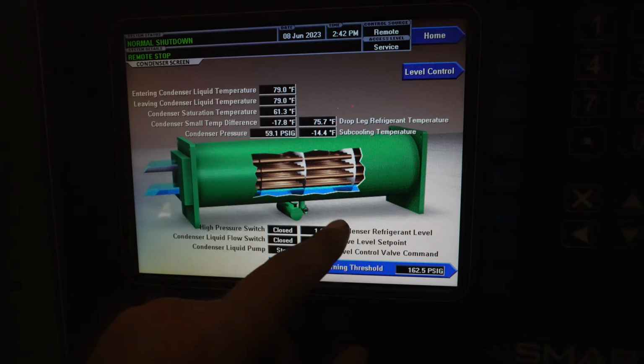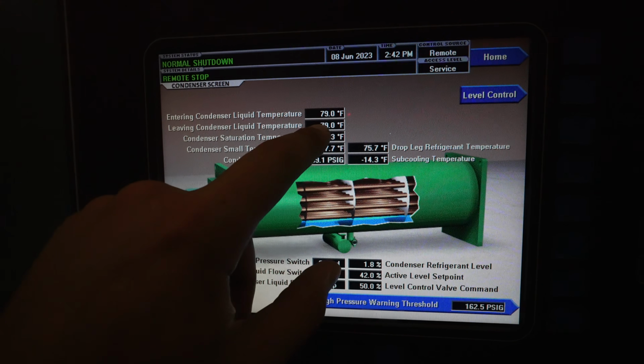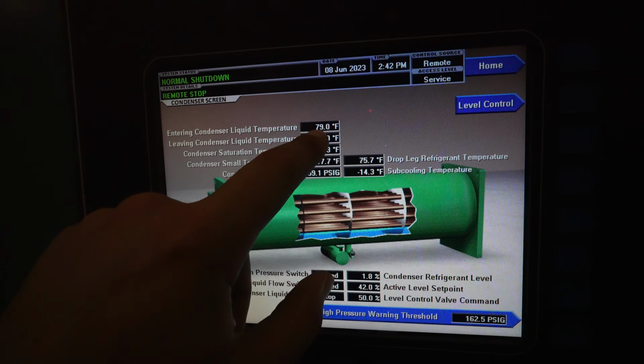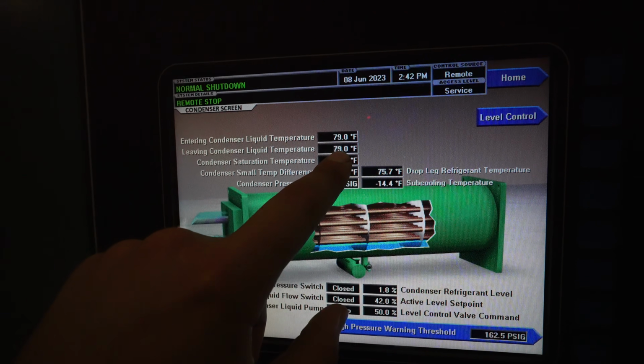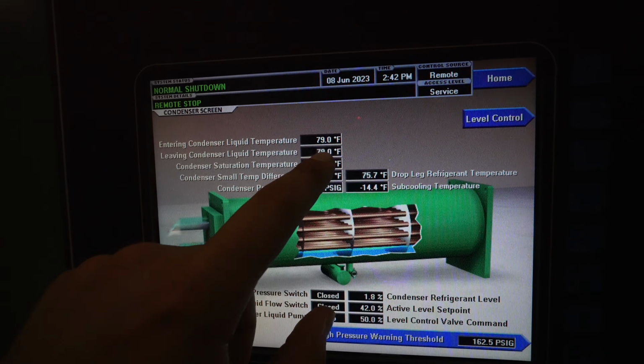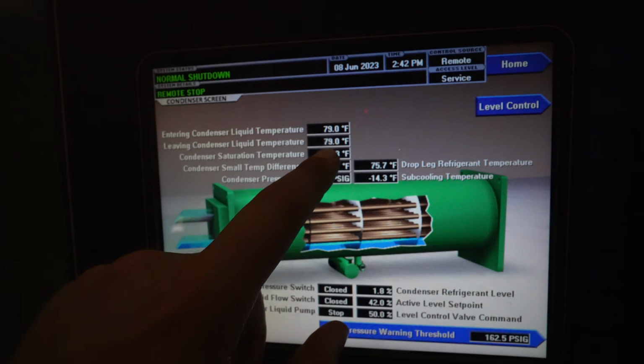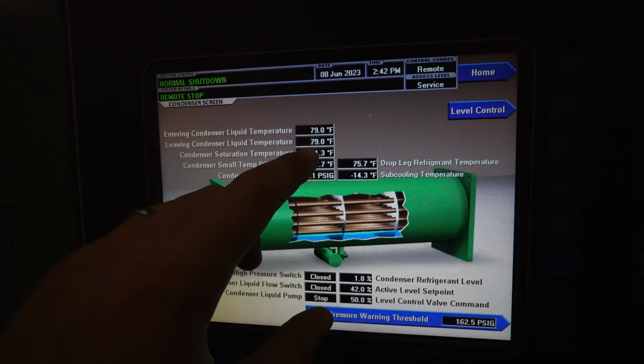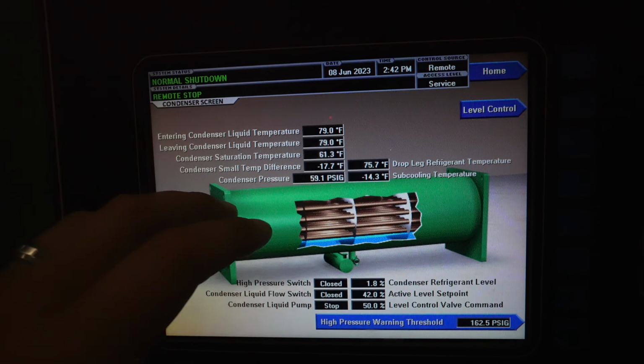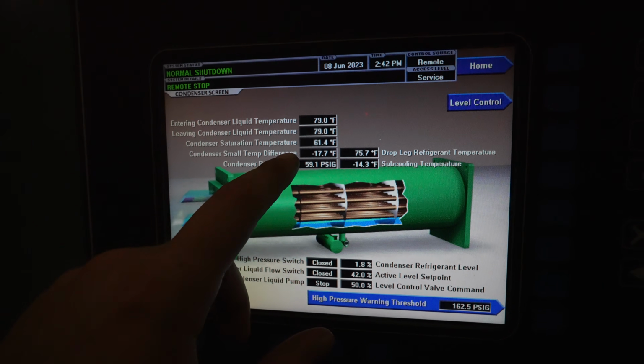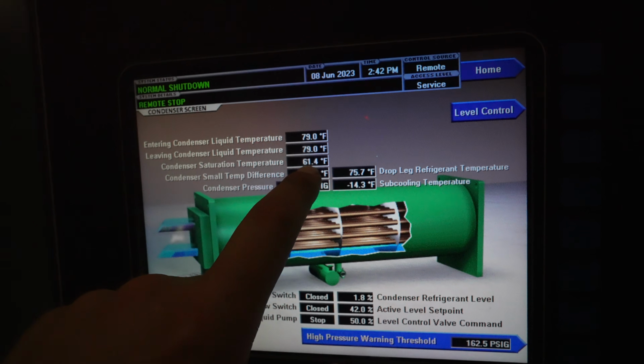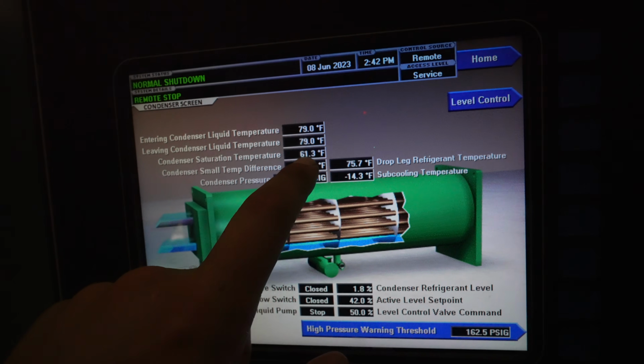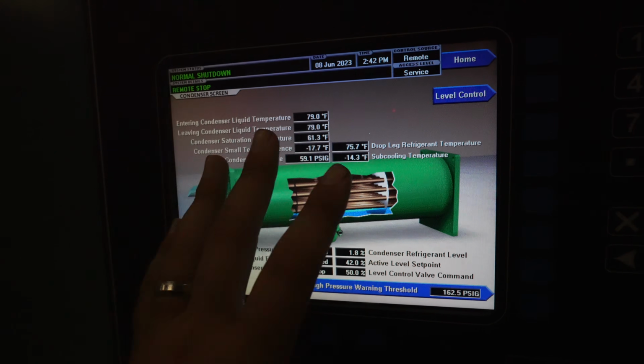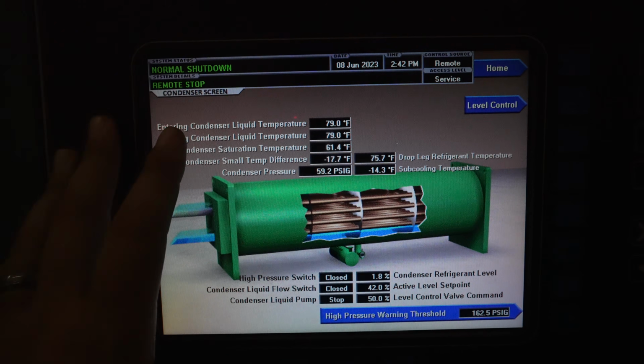the time. But one of the other things I was noticing was we were pushing in about 79-degree water, but we were pushing out right at 90 degrees of condenser water. So we had like a 12-degree split across our condenser. In addition to that, our saturation temperature was up about 95, which was excessively high for this machine. It does not typically run that much.